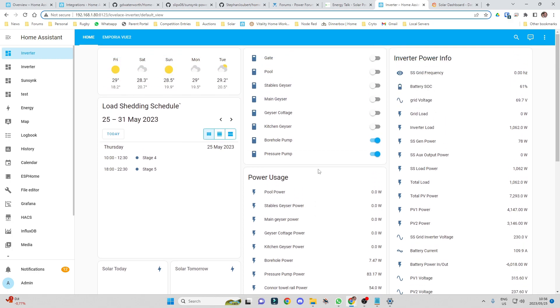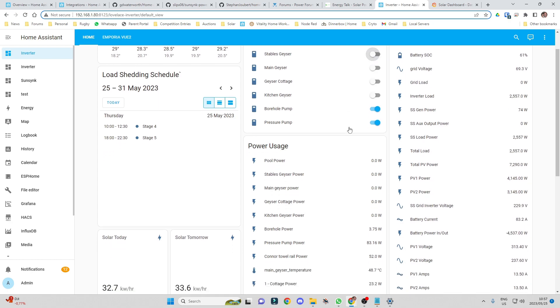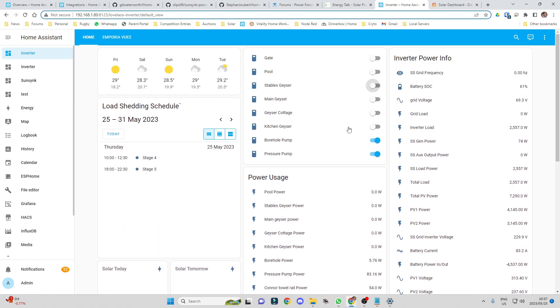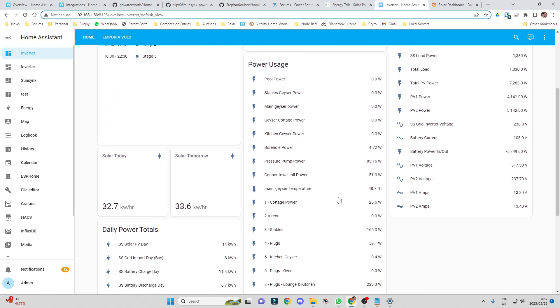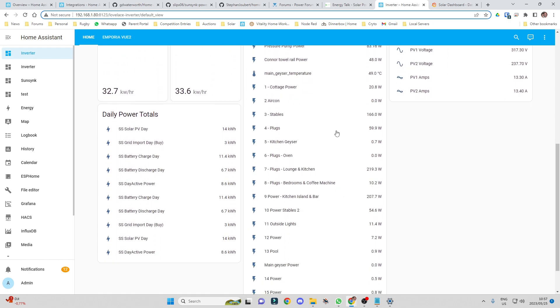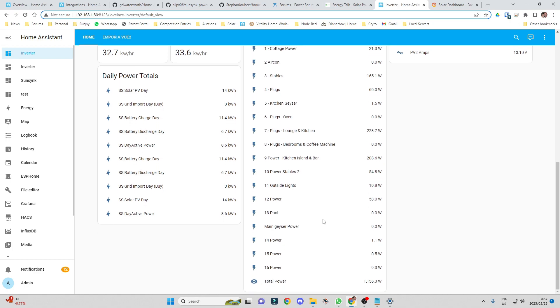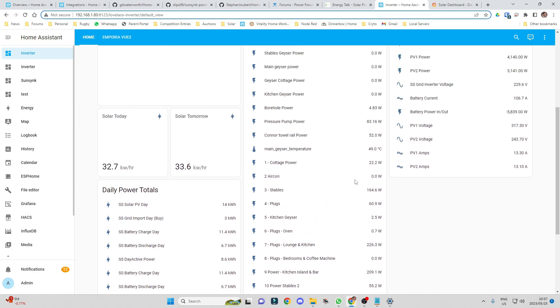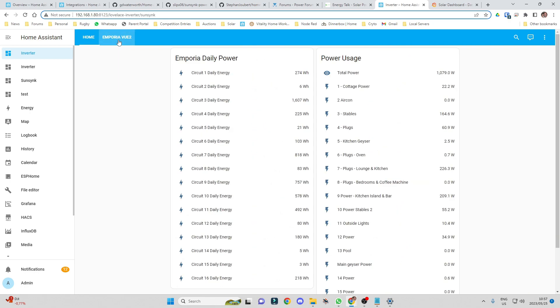If I turn my geyser on down there for example, you will see my geyser - that's the load that my geyser is putting, so it's almost instantaneous. What I also have is a device called an Emporia Vue - I'll insert a picture of that for you guys to see. It's a 16 port with 16 CT clamps. It clamps all of the breakers on my DB board and gives me my power usage over all 16 circuits of my DB board, so I can see exactly where the power is going, who's using how much power, and I also have a daily total.